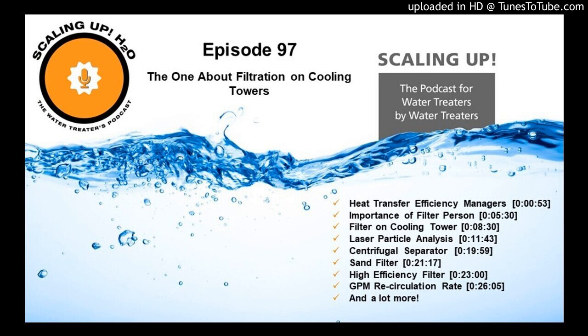Well, the customer's always looking at the bottom of the cooling tower basin, and some look at it more than others. I always say if there's more than a 1/4 inch of debris on that basin, it is past due for cleaning. So the customer's going to ask, if I put this filter on, can I extend the amount of time I have to clean my sump? Or some might even ask, can I forego cleaning my sump altogether now that I have this filtration? Yep, that's a good question.